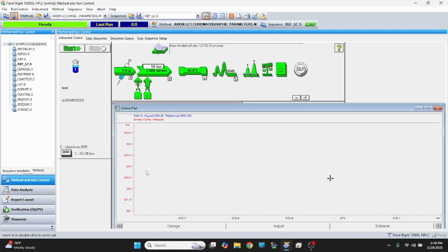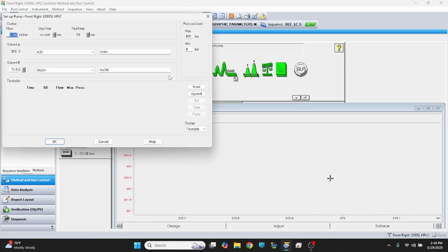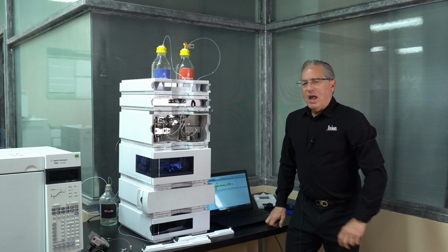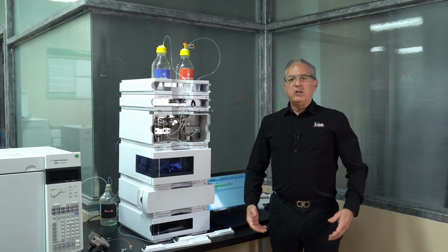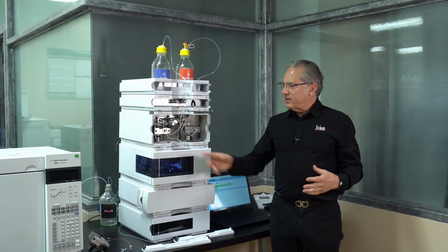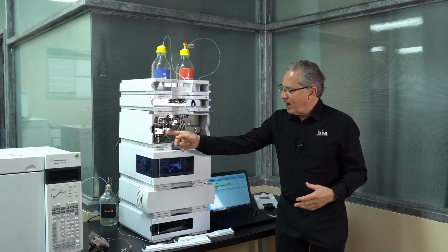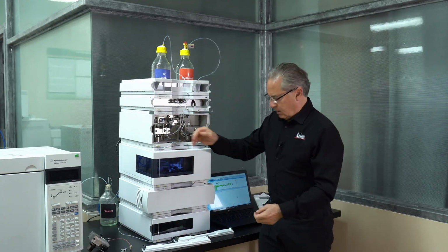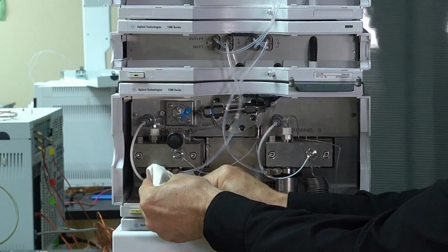So you open the purge valve, and then I typically turn the flow rate up to 5 mils a minute. So we're going to make that 5 mils a minute. I'm going to say OK. You can hear the pump has sped up, and now what it's doing is just pumping really, really fast through here, and it's coming right out the purge valve. I don't know if you can see it in the waste line. I could probably do this for you. If I pop this off, you'll probably see it dripping out very quickly, coming out of the pump.